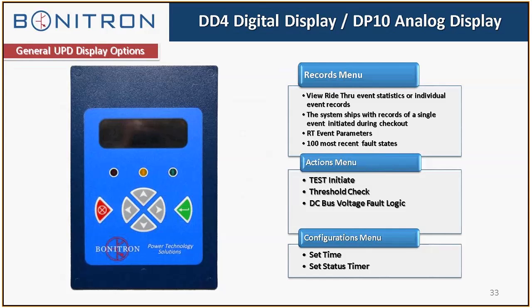Some of the parameters you can monitor with the DD4 display: ride-through event statistics, individual ride-through events, or lifetime ride-through events. So you can actually see what your utility power is doing or what your internal plant PQ is. So it may help you to be more specific about your requirements for later installations. Or it may cause you to realize that you need to retrofit the sag ride-through with outage ride-through ultracapacitors. Okay, the system will ship with a record of a single event, and that's what we use for testing. We test them with that and then ship them with the event logged into the DD4 display.